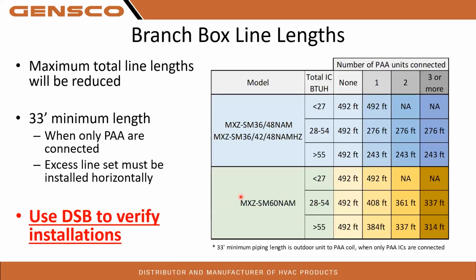Branch box lengths. You will see some different branch box length requirements when using the PAA coils. Your maximum line set distance is going to be reduced. Again, use DSB to verify these projects when you're building them to make sure you're building them within spec. And also, again, 33-foot minimum line set length when only PAA coils are connected. If you're using other equipment with the PAA, you don't have to have that minimum 33 feet. And that minimum 33 feet is total length, by the way. Any excess line set that's coiled up, again, has to be installed horizontally. Use DSB. Very important.